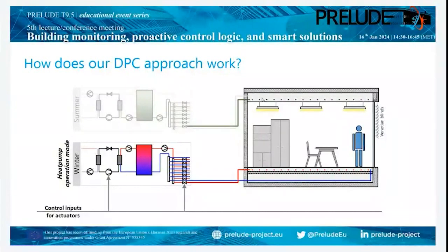We also get a value for the valves of the floor heating system, for example, and the power. So we get as information the heating power in each thermal zone, and we can use these inputs to write to the valves in the real building.